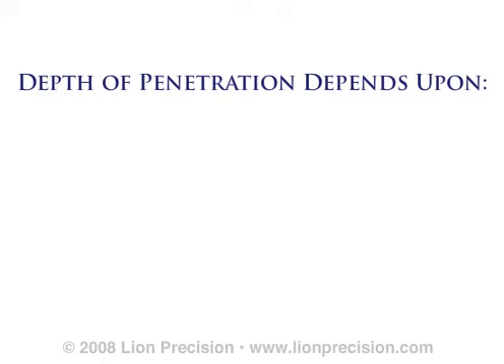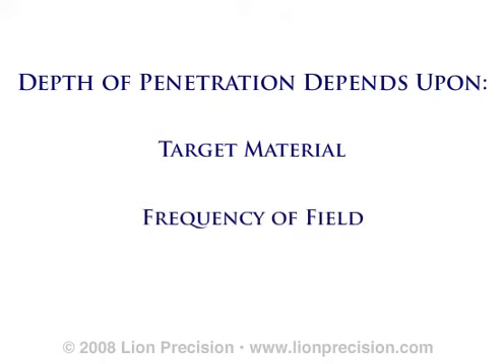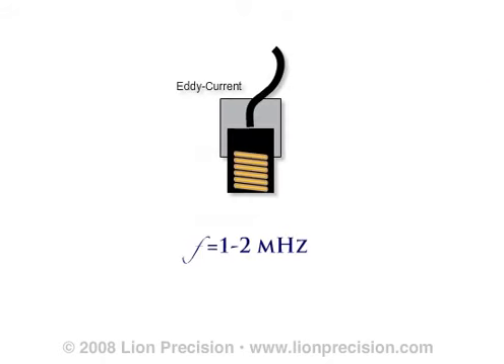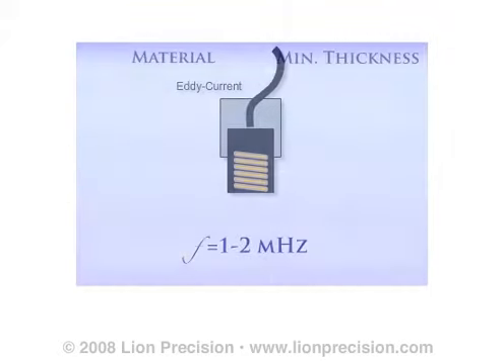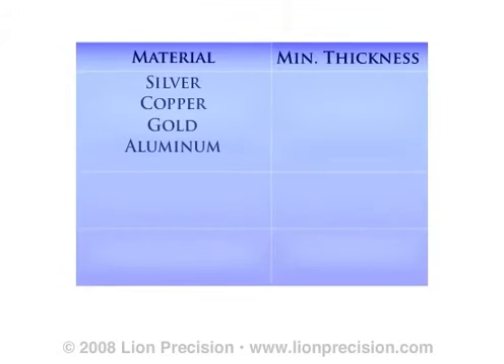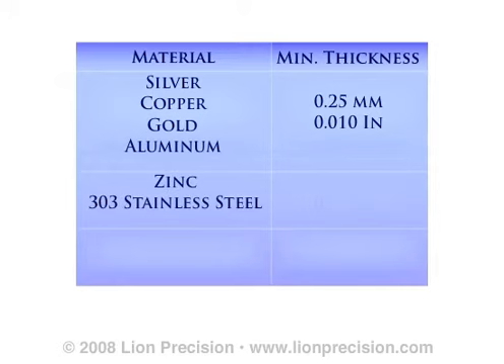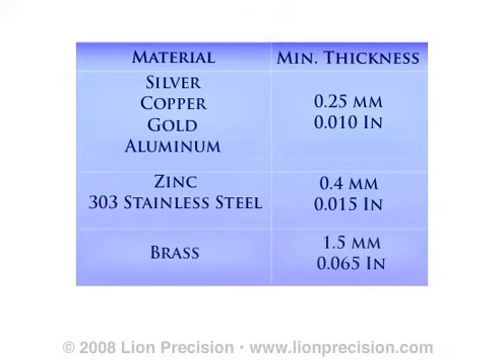The depth of penetration of the sensor's magnetic field is dependent on the material and the frequency of the sensor's oscillating magnetic field. Lion Precision eddy current sensors use a frequency of 1 to 2 MHz. At this frequency, some non-ferrous materials have the following minimum thicknesses. Silver, copper, gold, and aluminum require about 0.25 millimeters or 10 thousandths of an inch. Zinc and 303 stainless steel need about 0.4 millimeters or 15 thousandths of an inch. Brass has a comparatively large minimum thickness of about 1.5 millimeters or 65 thousandths. More detail can be found on the minimum recommended target thickness tech note at lionprecision.com.